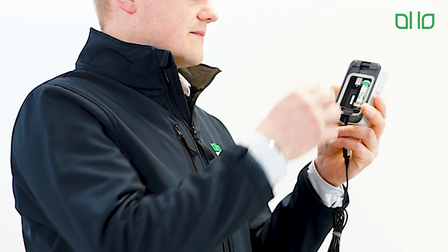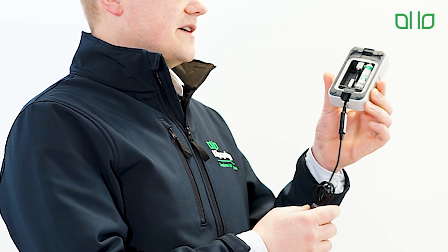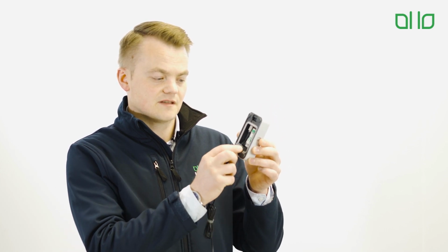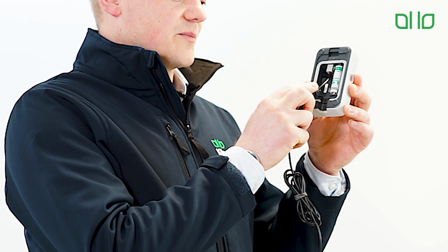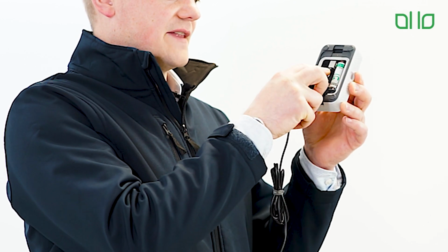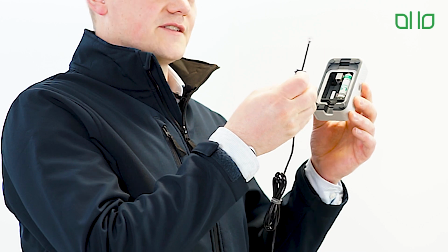The second issue you may come across is a damaged probe, and this probe may need replacing. This may be signified by an open circuit on the system or faulty readings after a calibration. To replace the probe, simply remove the sensor from the factory and locate the back housing, remove the clip and the back plate, and you will find the probe located and connected into the back of the transmitter. There is a waterproof compression gland which you will remove, and then a small clip to undo the probe.